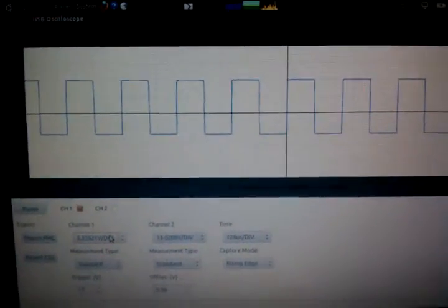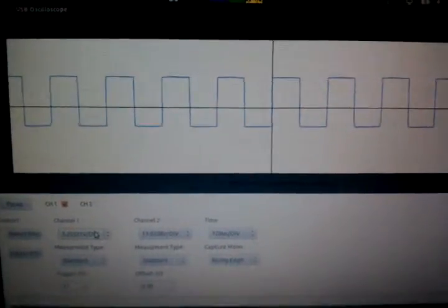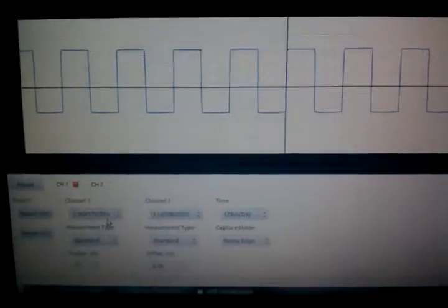So here is 10 volt peak to peak. You can see on both our oscilloscope and the TriggeringTest oscilloscope that we are now at 10 volts peak to peak. A little low actually. And we go back. There we go, 10 volts.